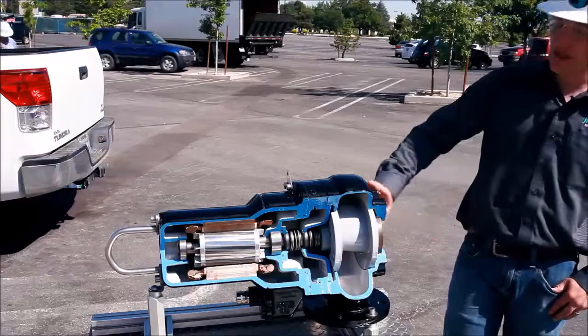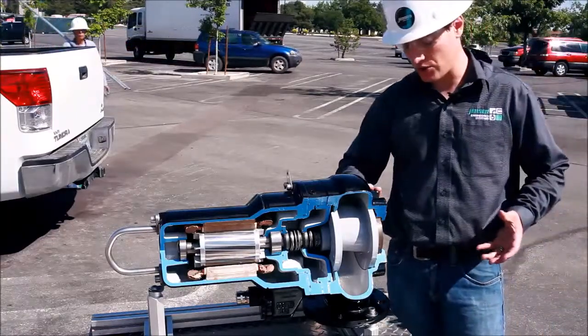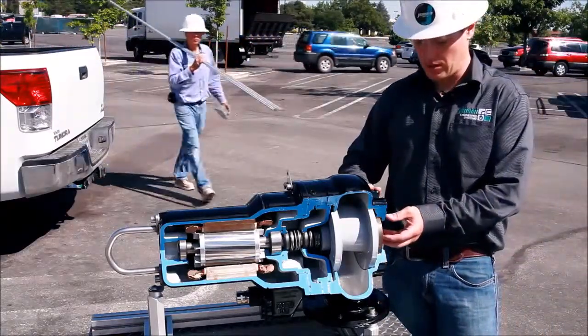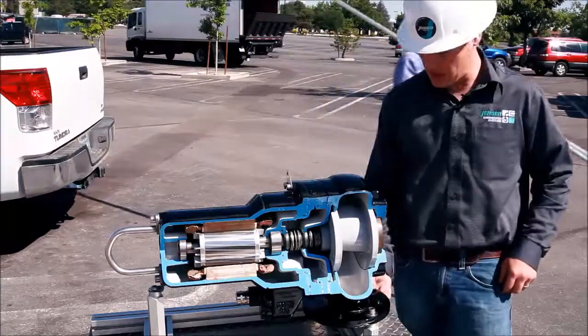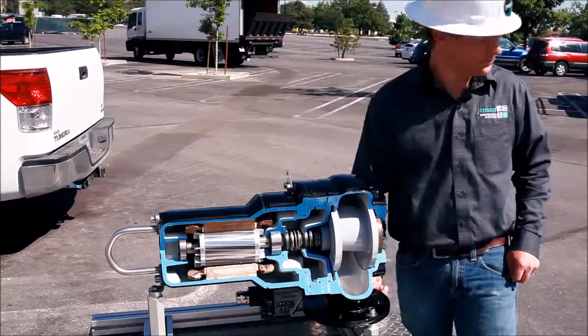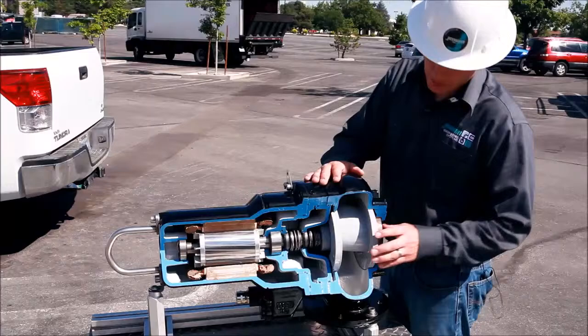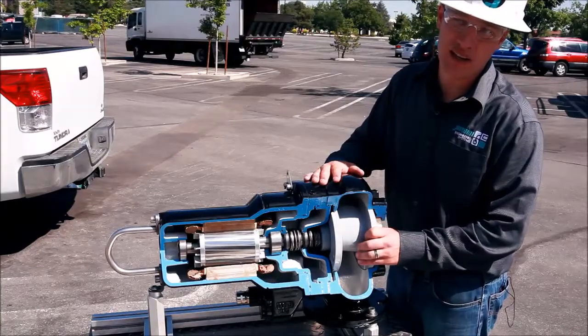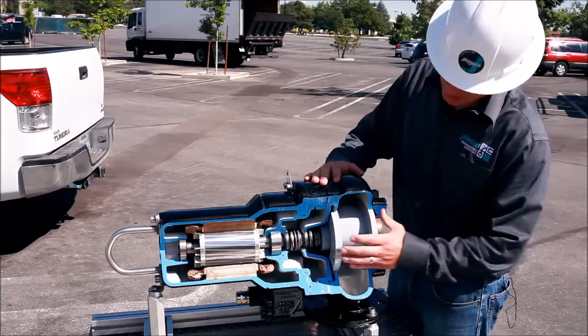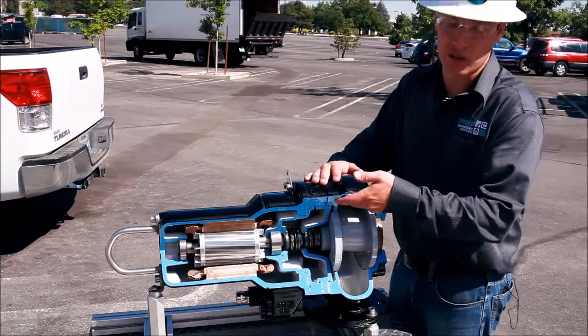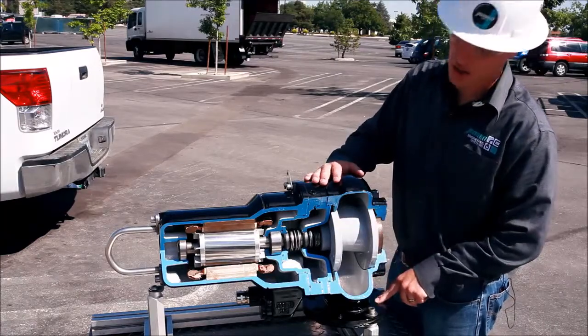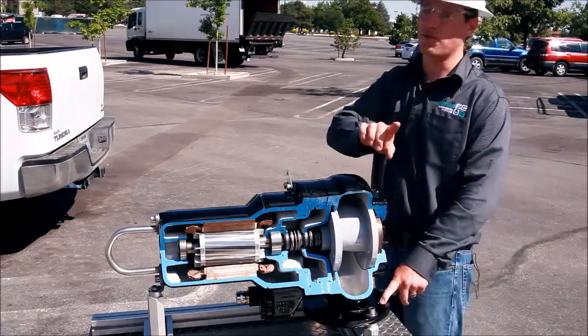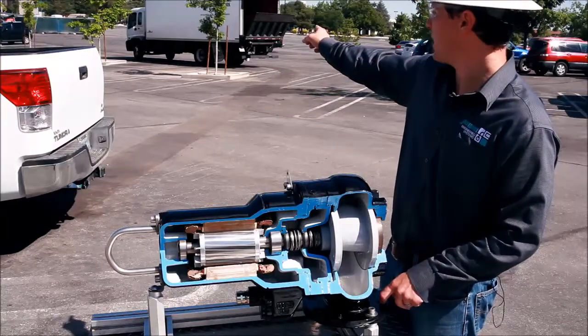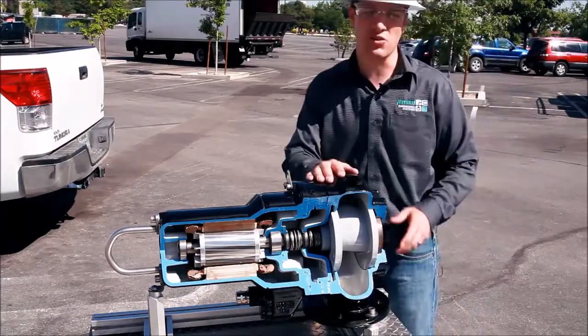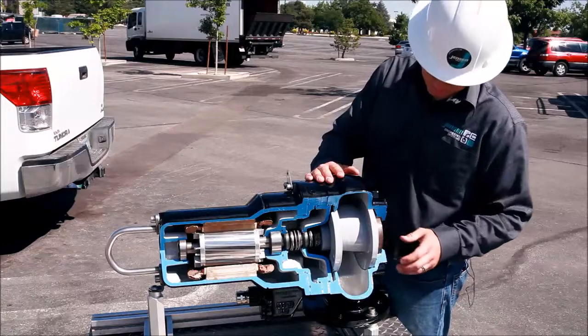The inlet of the pump is down here on the bottom of the pump. All sewage is going to enter the inlet right here at the bottom and be discharged out this discharge flange right here. This is made possible by the rotating impeller. This is what's going to be adding energy to the fluid. This impeller is rotating and pushing the fluid against the volute, then forcing the fluid out the discharge flange through our force main pumped 400 feet directly behind me to the city's gravity sewer main.